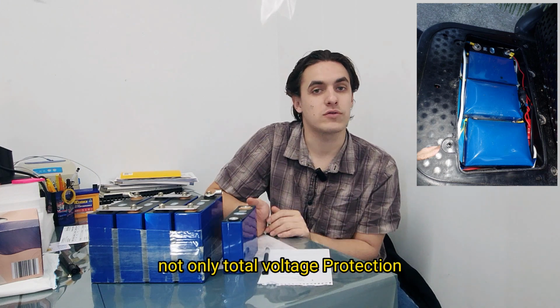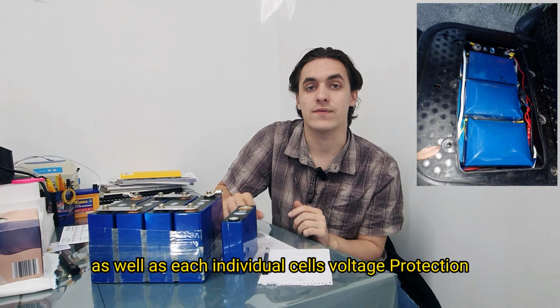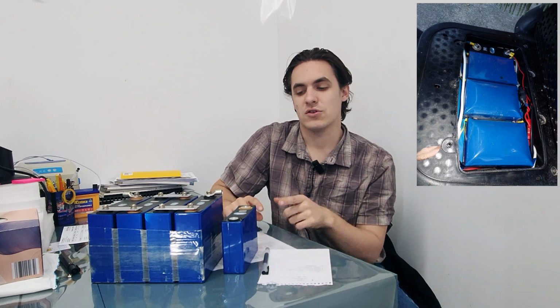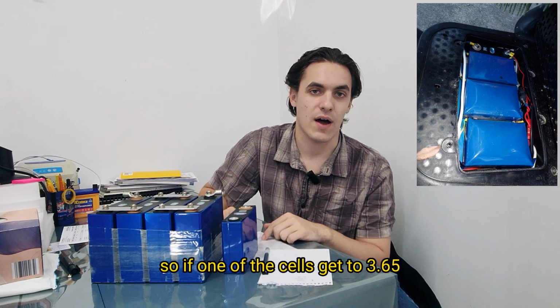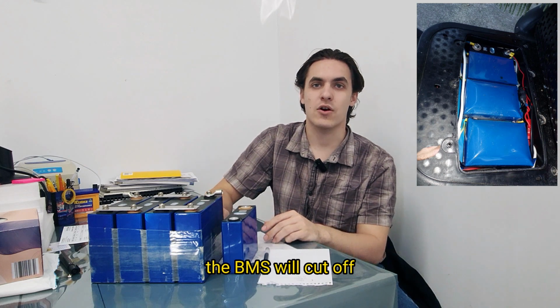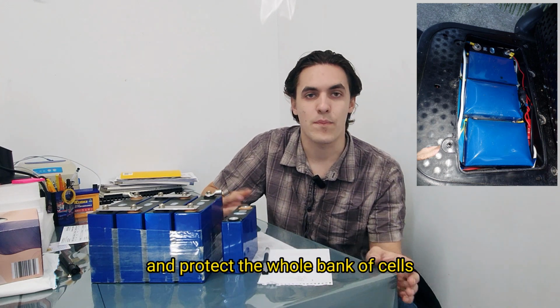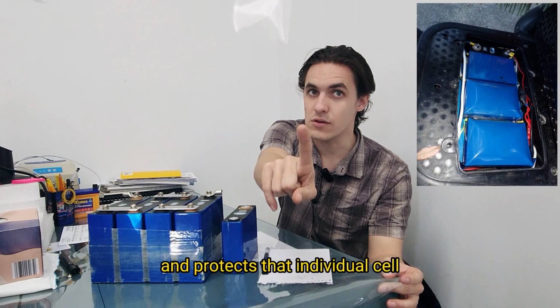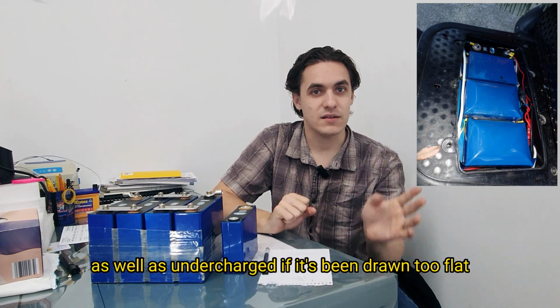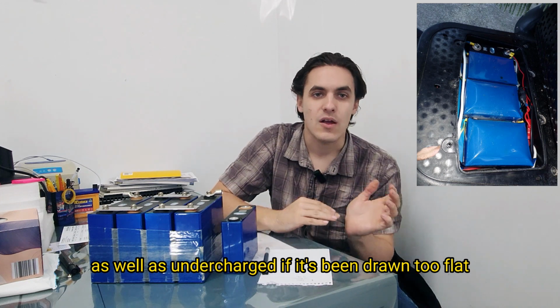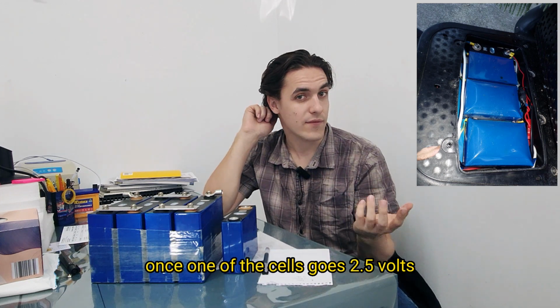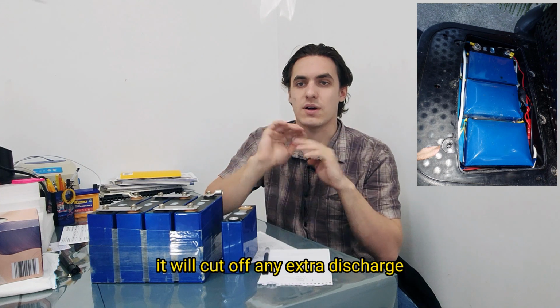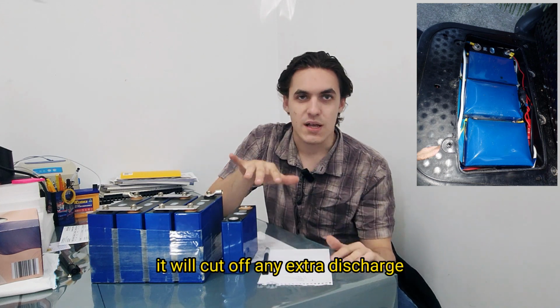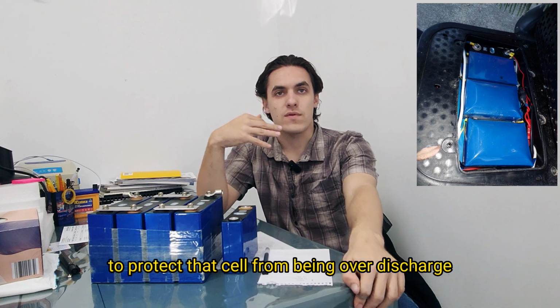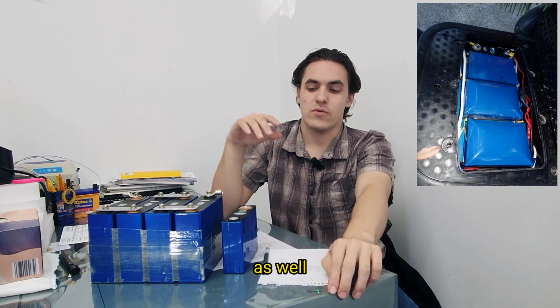Another function of the battery management system is voltage protection, not only total voltage protection but each individual cell's voltage protection. So if one of the cells reaches 3.65 volts, the BMS will cut off and protect the whole bank of cells, protecting that individual cell from being overcharged. As well, if it's drawn too flat, once one of the cells goes down to 2.5 volts, it will cut off any extra discharge to protect that cell from being over-discharged.